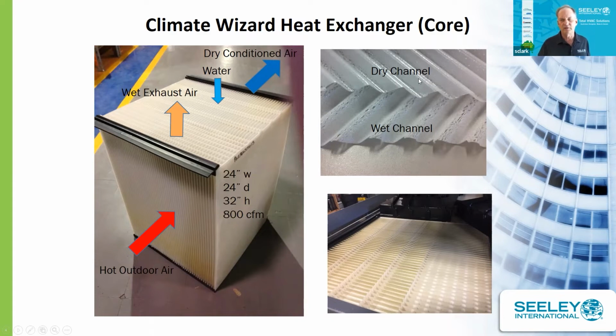If we look at a close-up view of our wet and dry channels, we have this plastic with convolutions on it to create highly turbulent airflow. And then we have wet channels, which is the same sheet as the dry channel, but it has a special material in here that wicks up the moisture and allows good heat transfer from the dry channel into the wet channel. So this is a proprietary patented heat exchanger that allows us, again, to go below the wet bulb temperatures. Here's another close-up view with it in the unit.